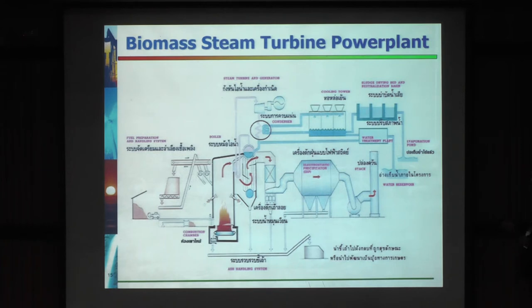Hot flue gas will pass to the boiler, where we heat up the water to produce steam. Steam is used to drive the steam turbine and the generator to produce electrical power. For the flue gas treatment, we use the electrostatic precipitator, which is most commonly used to control the dust. For SOx, or SO2, actually in biomass there is a very low percentage of sulfur compared with coal. So actually we can control the type of biomass to control the SO2. For the NOx, the combustion temperature inside the furnace is also not so high, so we can also control the NOx emission.